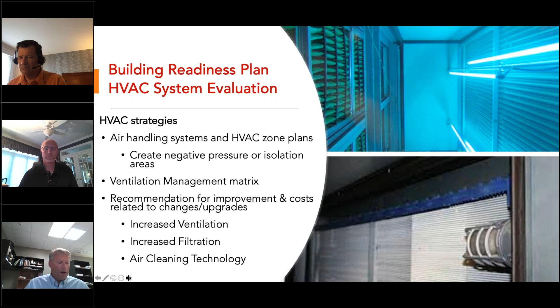So, talking about improving indoor air quality, there are a lot of different things we base that on: the building use, the HVAC system, all the different types, and the age of the HVAC system. I just did a study a couple of months ago where they wanted to increase MERV ratings and see what we could get on filters. I took one look at the air handlers, and I should have put a picture in there. The filter racks were so badly damaged that there was no sense putting in a higher MERV rating, because essentially half the air was going around the filter racks because of the damage over 35 years of that air handler. So we recommended you need to replace at least the filter racks and probably your whole air handler before we start looking at increased filtration.